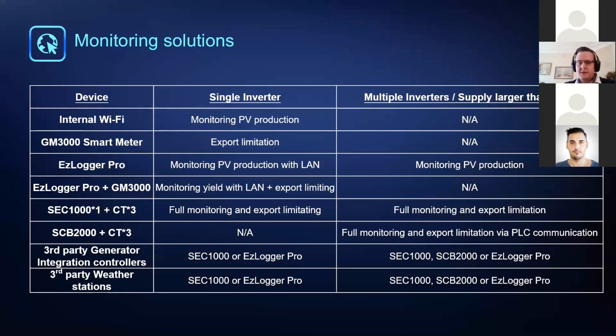And the SCB2000 then comes into play once you've got a transformer isolated system. Then you can have the full monitoring and export limitation with the PLC communication. So this does require a transformer isolated system, so no loads in between the inverter and the actual transformer. The third-party controllers also work with the SCB2000. So all of our monitoring products support the third-party generator controllers and weather stations.